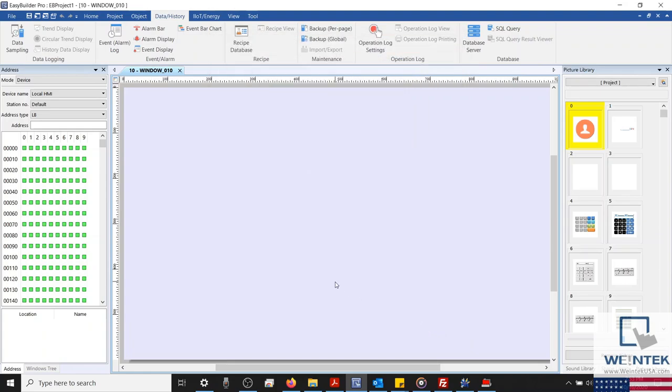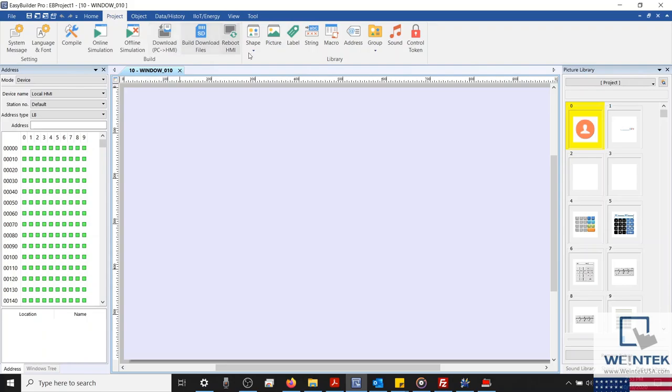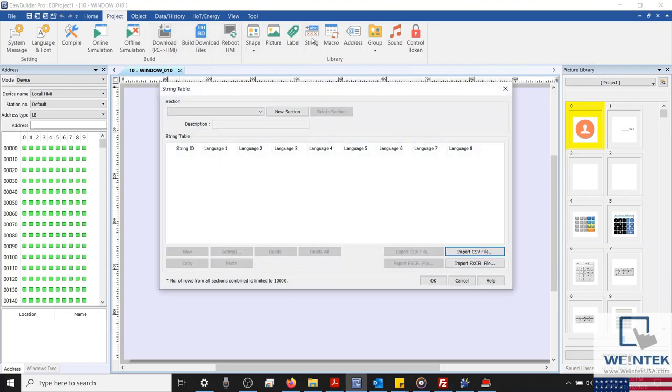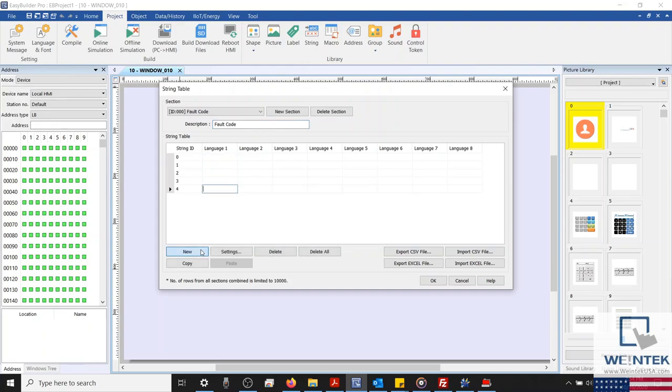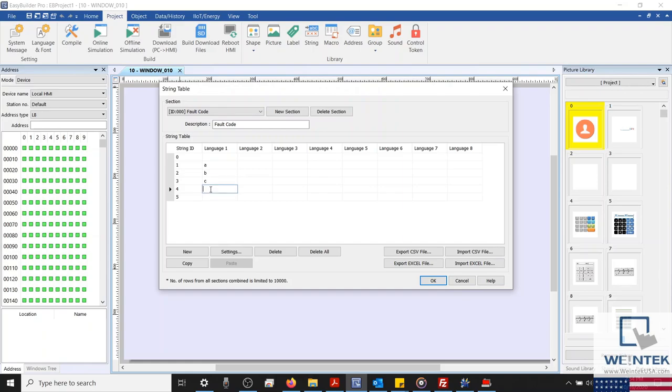To access our string library, we'll select the Project tab and select String within the Library section on the right-hand side. I'm going to select New Section and give this section a name. I'll call this Fault Code. Now, I've been asked several times if there is a way to have an alarm's message depend on the value within its read address. Well, using the string library, we can define a section of dynamic entries. I will label them alphabetically so that we can monitor the state change in real time. I'll leave state 0 blank in this example, and I'll create a total of five states.